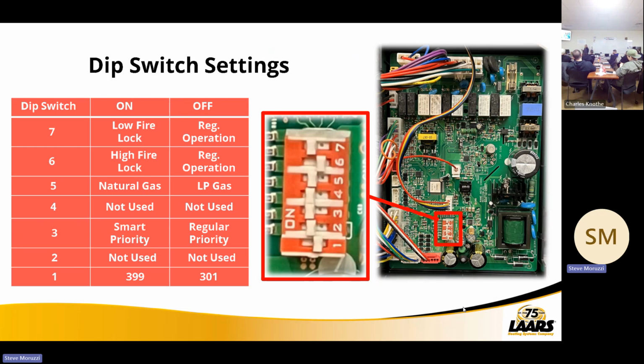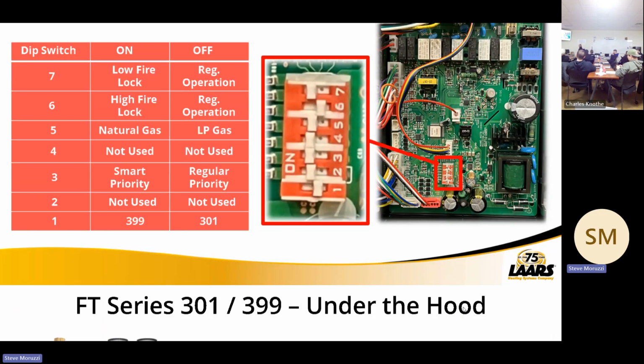Dip switch 6 and 7, those are your dip switches for high and low fire. And John's point earlier, if you leave that in an on position, such as shown here, dip switch 7 is in the on position for low fire. When you walk away, you're stuck in low fire. So make sure those dip switches are back in the off position when you're done with your combustion analysis.